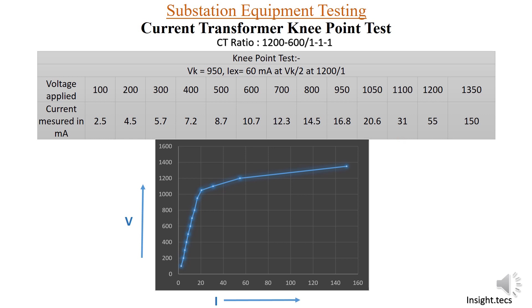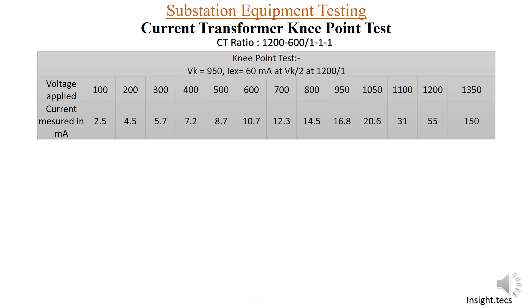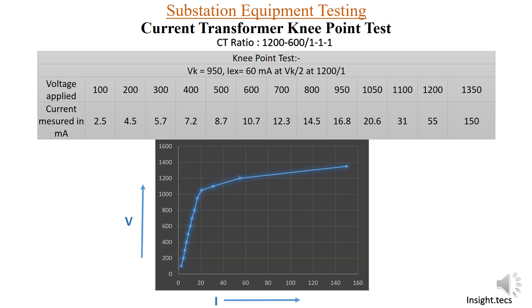The graph of results is similar to the knee point voltage graph seen earlier. Up to 950 volts, the current increase is steady and slow, but after 950 volts — beyond the knee point — the current increases very rapidly. This is the CT saturation region, which may damage the core. That is how the knee point voltage test is performed.